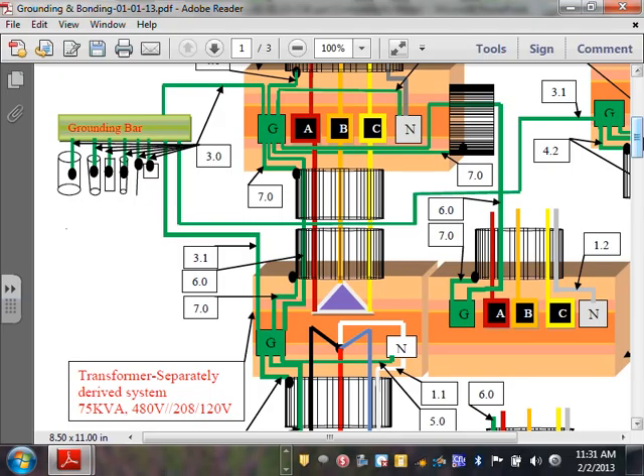Can you use a full water pipe as an electrode, and go to that instead of going all the way back to the building's electrode? The only question is whether it is bonded all the way. The steel is going all the way. The water pipe is already bonded to the service. The plumber doesn't. Yeah, see, that's the reliability.